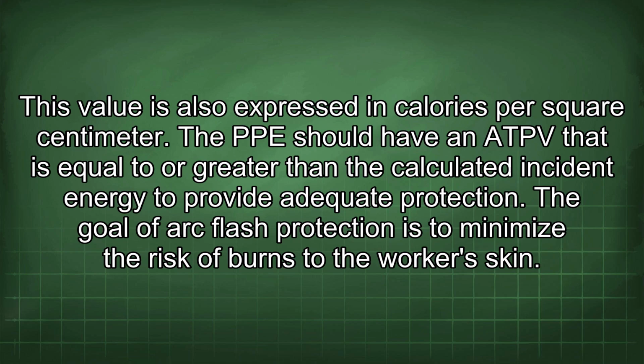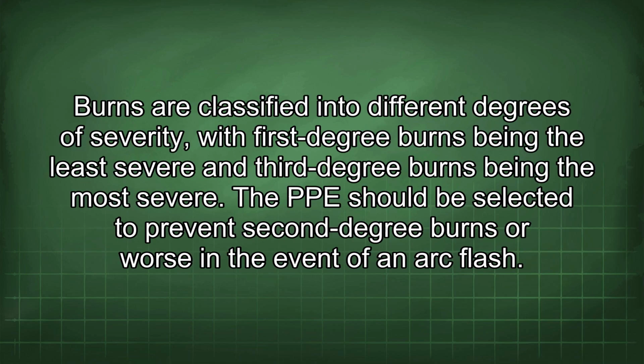The goal of arc flash protection is to minimize the risk of burns to the worker's skin. Burns are classified into different degrees of severity, with first-degree burns being the least severe and third-degree burns being the most severe. The PPE should be selected to prevent second-degree burns or worse in the event of an arc flash.